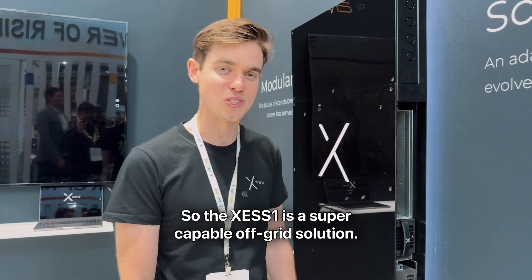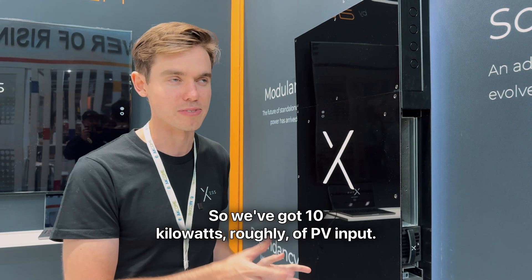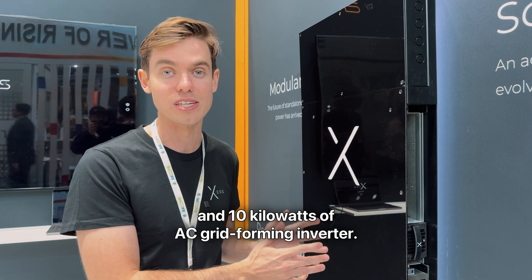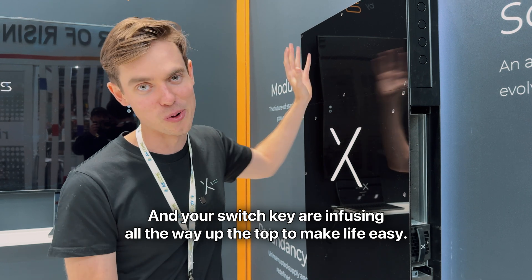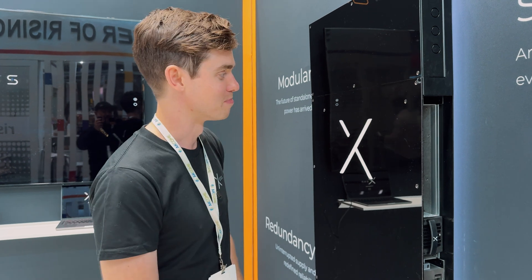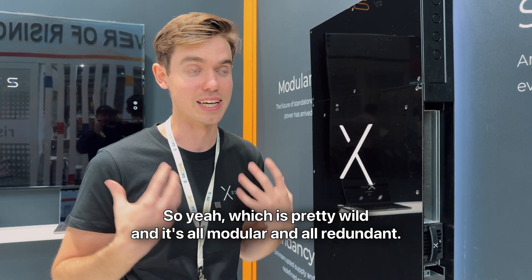The XESS1 is a super capable off-grid solution. We've got 10 kilowatts of PV input, oversizable up to about 15 with two modules, and 10 kilowatts of AC grid-forming inverter. Your switchgear and fusing all the way up the top to make life easy, so you don't have to actually think about what you have to do when you're putting it in. It's all modular and all redundant.